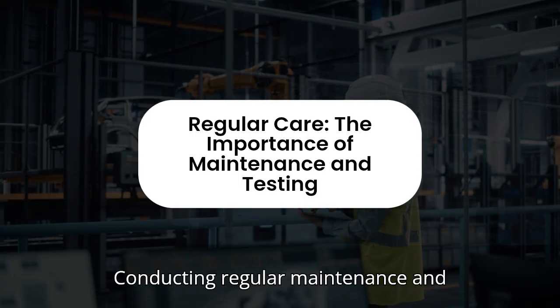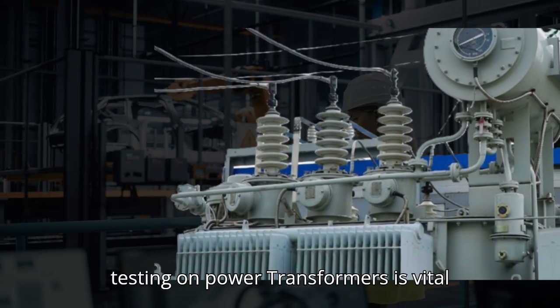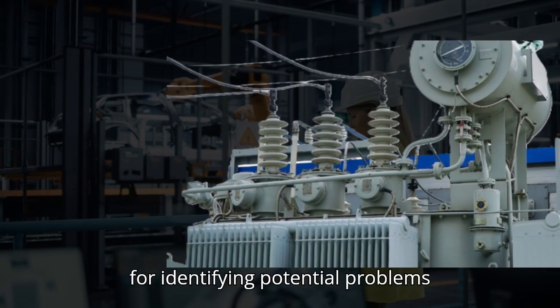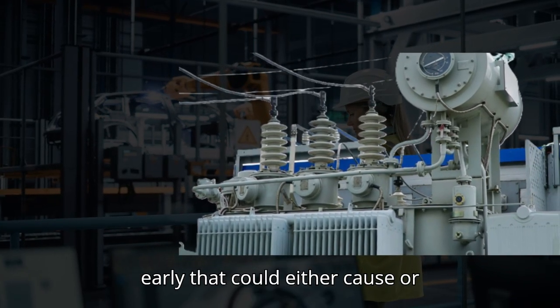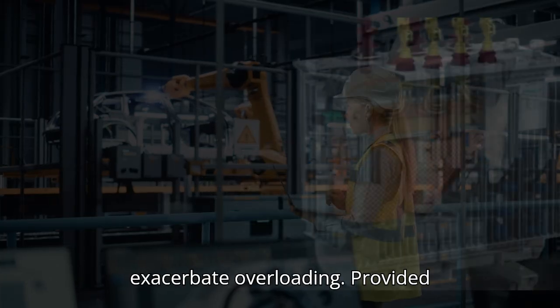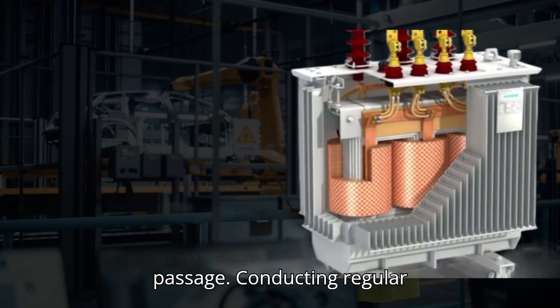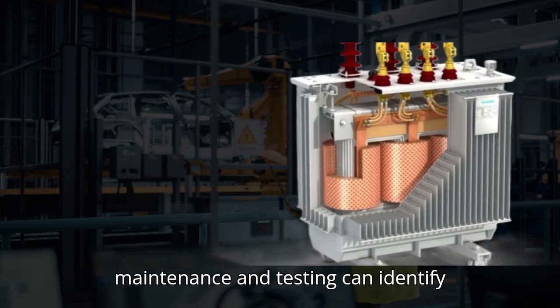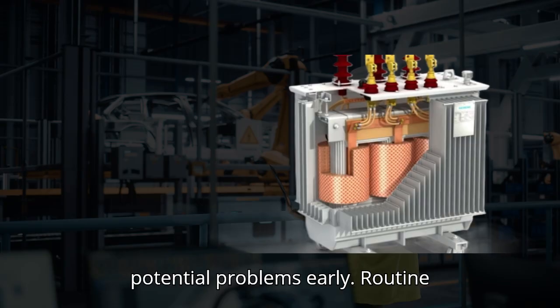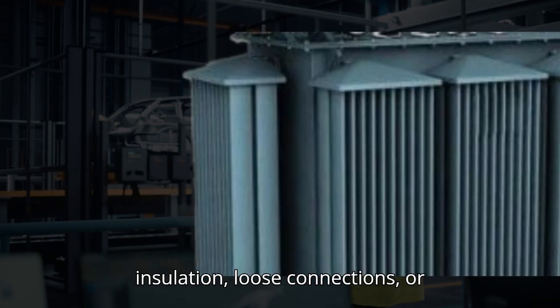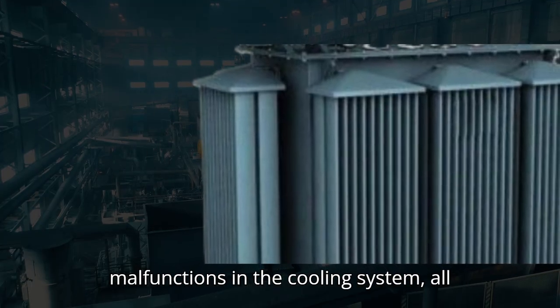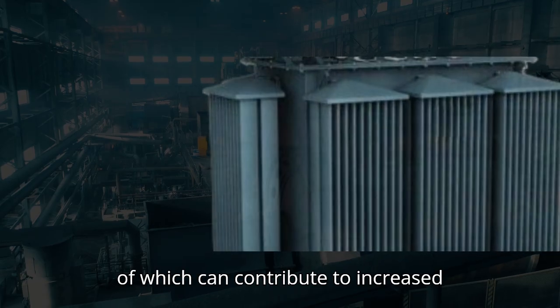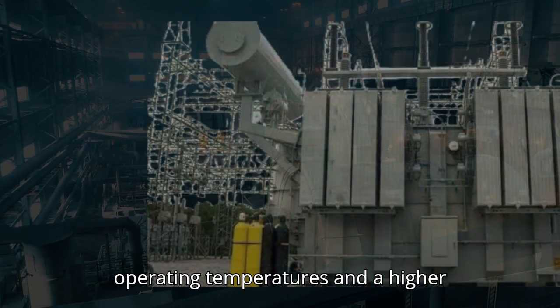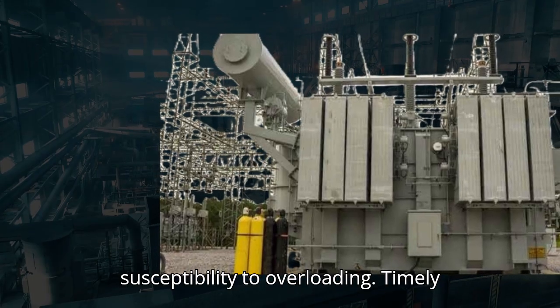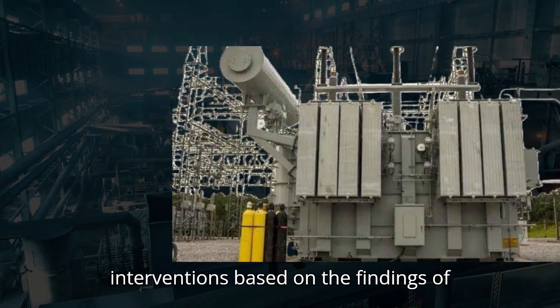Regular care. The importance of maintenance and testing. Conducting regular maintenance and testing on power transformers is vital for identifying potential problems early that could either cause or exacerbate overloading. Routine checks can reveal issues such as degraded insulation, loose connections, or malfunctions in the cooling system, all of which can contribute to increased operating temperatures and a higher susceptibility to overloading.